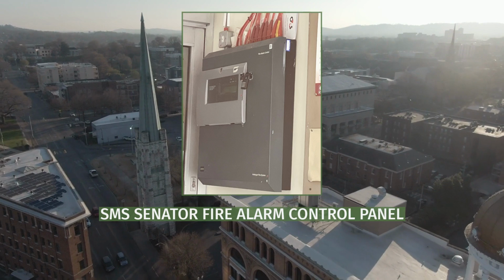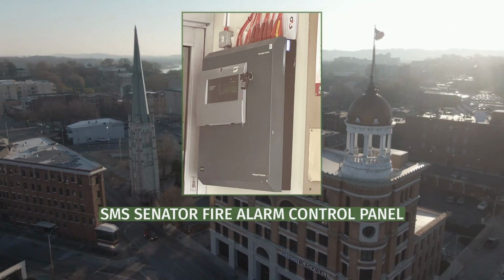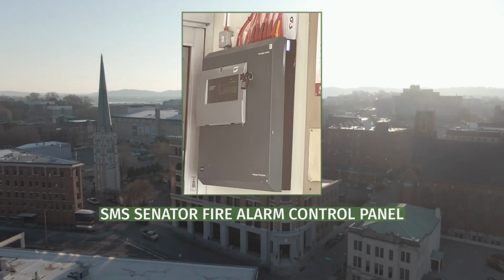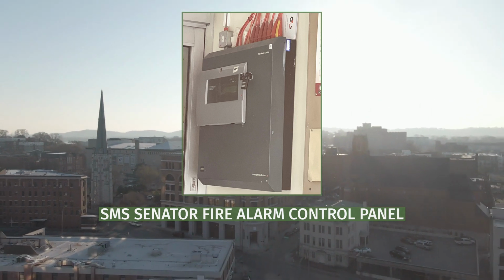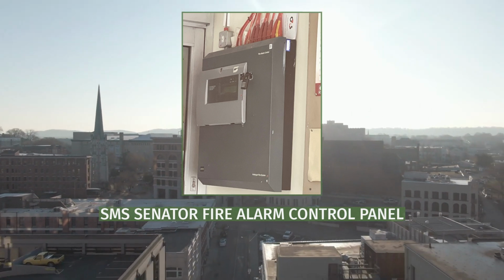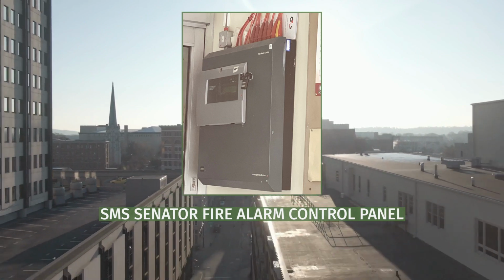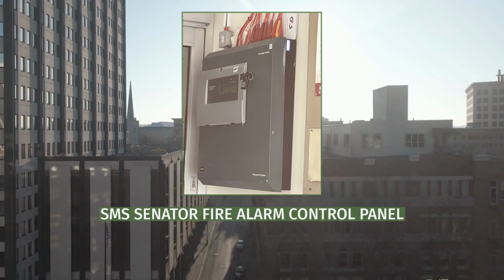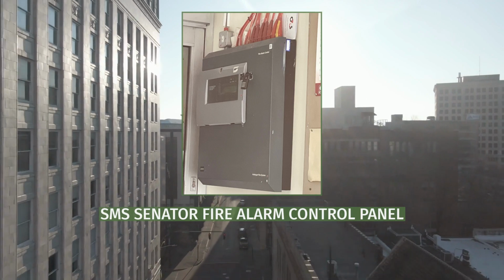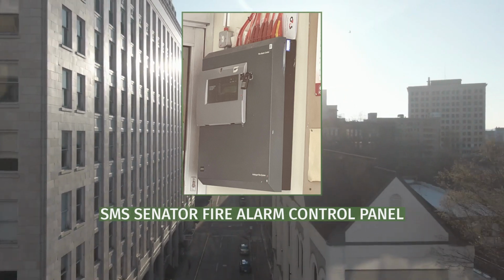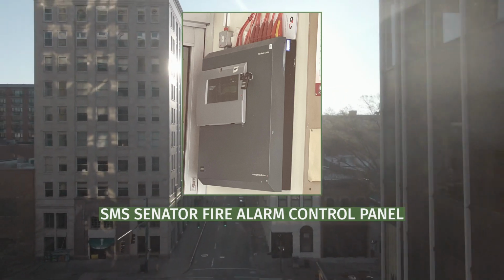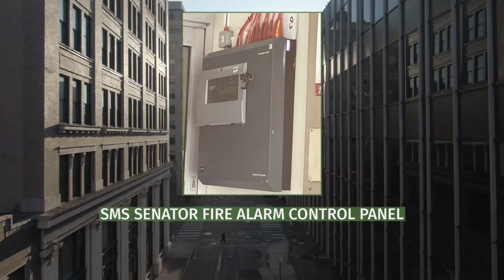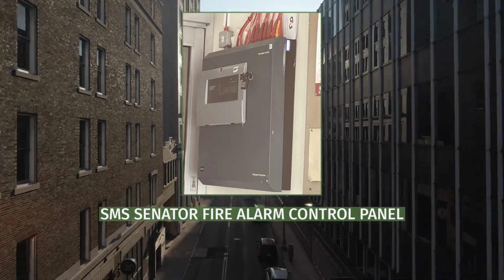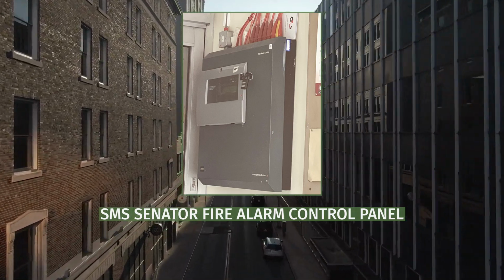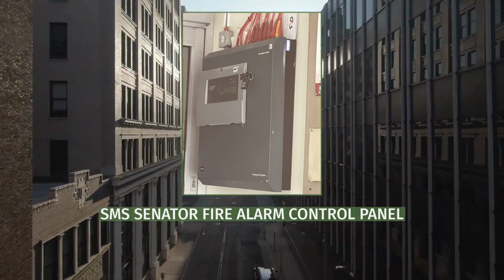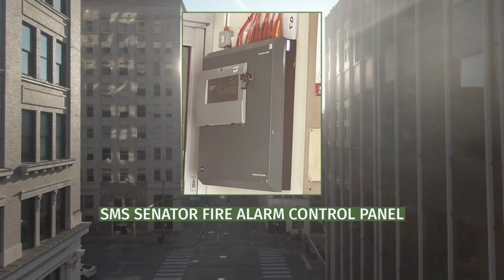System 32000 devices had a similar appearance to System 34000 devices, but model numbers began with 32 instead of 34. Some devices had slightly changed model numbers to their 34000 equivalents, such as the 32775 optical heat sensor sounder, whose System 34000 equivalent was the 34770 optical heat sensor sounder. These devices were the first ever combined sensor sounder to be released by Gent.